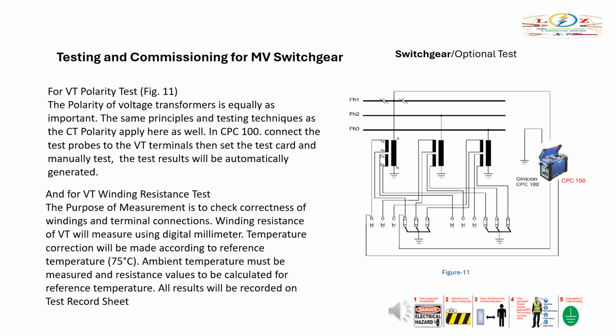And for VT winding resistance test, the purpose of measurement is to check correctness of windings and terminal connections. Winding resistance of VT will be measured using a digital multimeter. Temperature correction will be made according to the reference temperature, 75 degrees Celsius. Ambient temperature must be measured and resistance values calculated for the reference temperature. All results will be recorded on test record sheet.